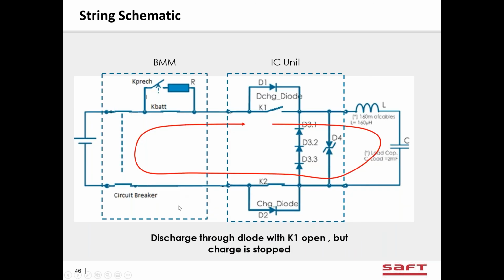So this is a schematic of how the battery system works with the BMM, the modules, and the IntelliConnect unit, or the protection device. And you can see on the right-hand side, the battery goes first through the BMM, and that's where the circuit breaker is. In there, there's also a contactor. This is how we turn the battery on and off.